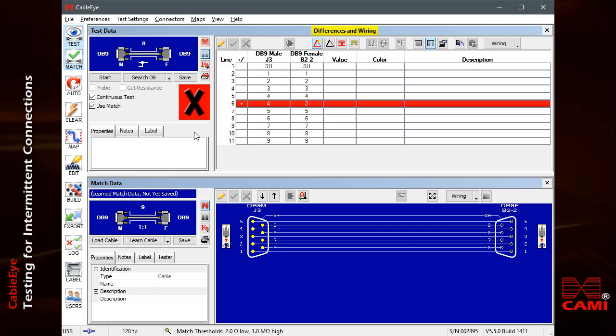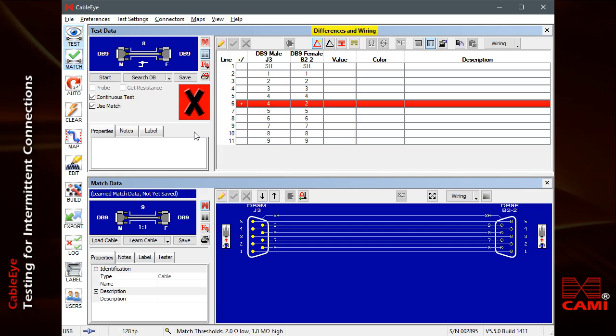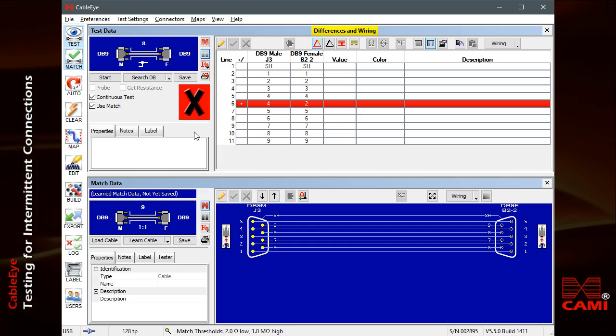If you suspect a particular conductor of having an intermittent connection, you may highlight that conductor in the schematic, and continually measure the resistance of just that conductor as you flex the cable.